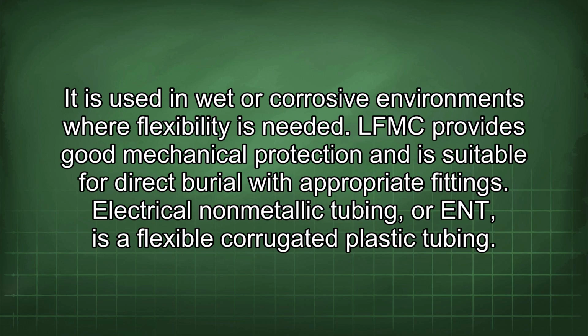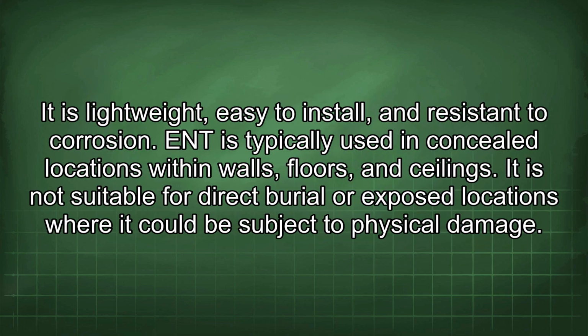Electrical non-metallic tubing, or ENT, is a flexible corrugated plastic tubing. It is lightweight, easy to install, and resistant to corrosion. ENT is typically used in concealed locations within walls, floors, and ceilings. It is not suitable for direct burial or exposed locations where it could be subject to physical damage.